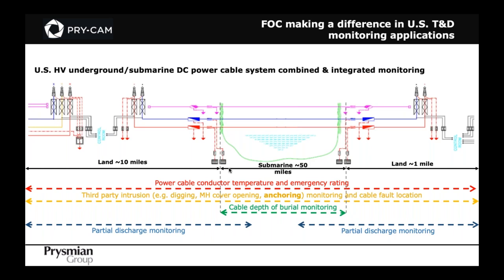There are cases where we have retrofitted fiber optic cable after the fact, in existing duct banks or conduits with medium voltage or high voltage assets. The economics really depends on the willingness and need of the end user and utility to do monitoring, compared to potential faults and cost of outages.